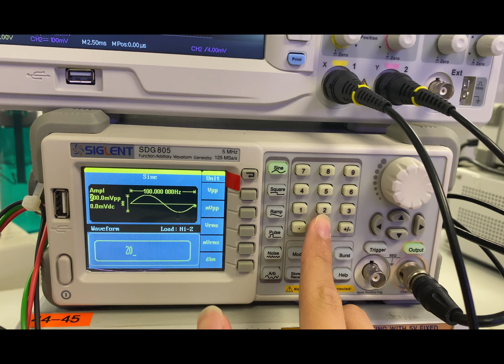Then, set the amplitude to 200 mV peak to peak, which can be done by pressing the amplitude, typing out 200 on the keypad, and then selecting millivolts peak to peak. Once everything is set, you can hit the output button to inject the signal into the circuit. To test stage 1, connect the probe of channel 1 to test point 1 and the output to test point 2.